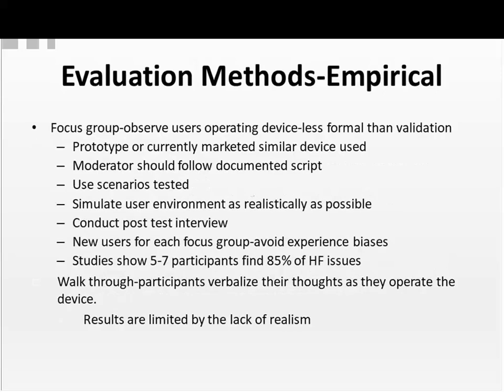Empirical methods. The focus group, where you observe the users operating the device. Now, this focus group is less formal than a validation focus group. In this study, you can use prototypes or a currently marketed similar device. You're trying to learn about it.